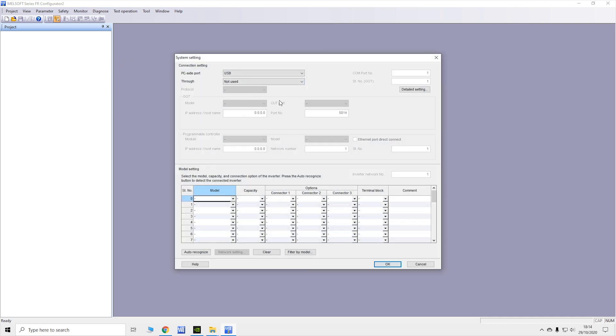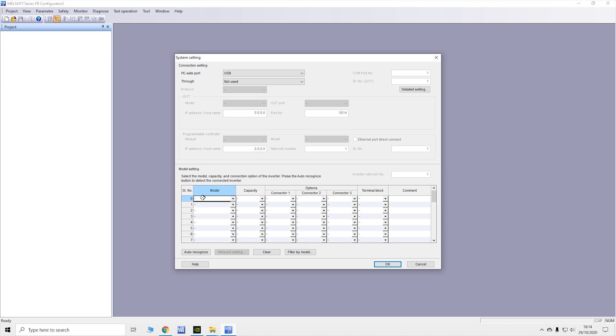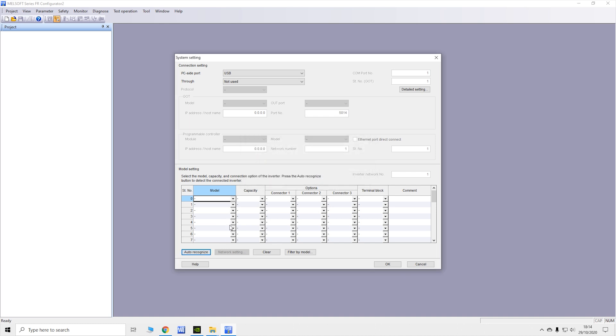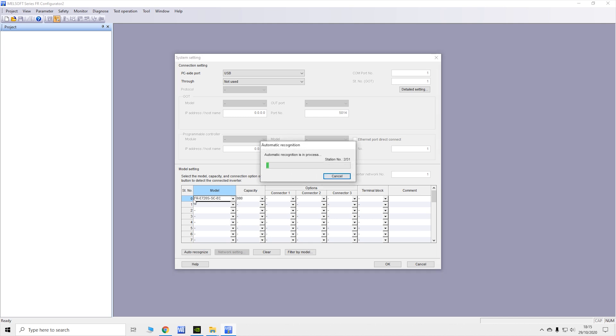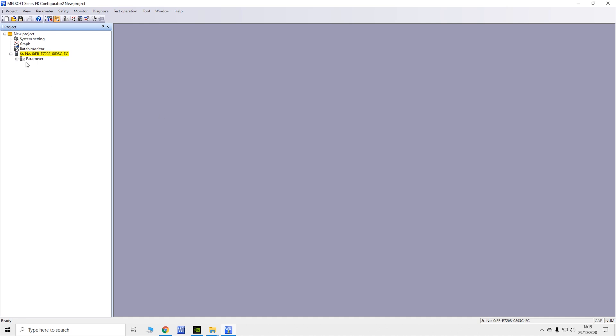Start a new project. In this window, if you're using USB you simply select that option. For the FR E series, everything should work fine with just the USB alone. You can manually find your drive if you wish — there are loads of options — but we're going to use Auto Recognize. Once you click Auto Recognize it will start searching for drives. As you can see, my drive is found. I only have one drive connected, so click OK and you are now connected to the drive.